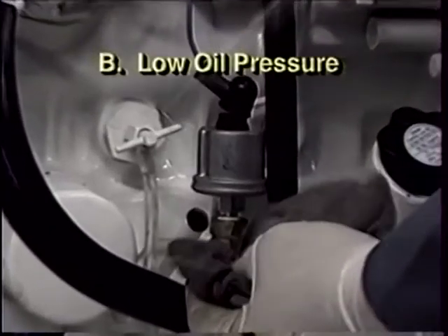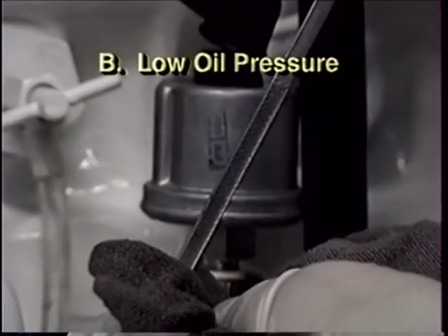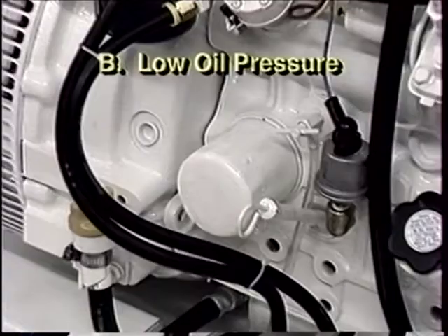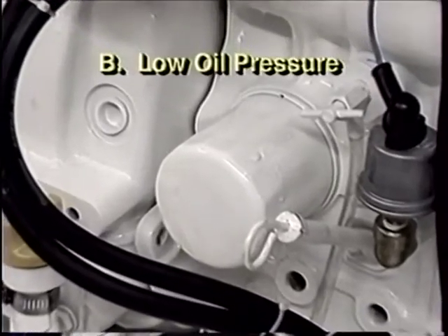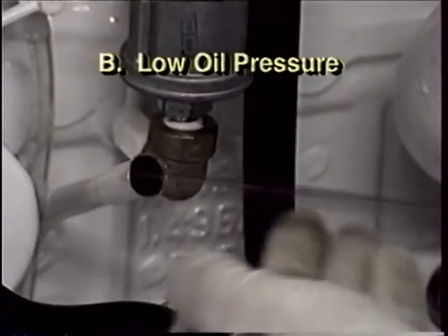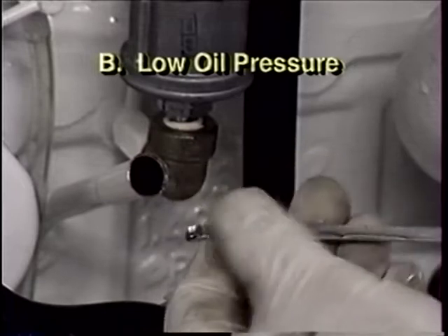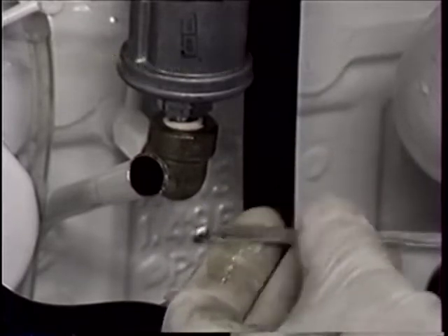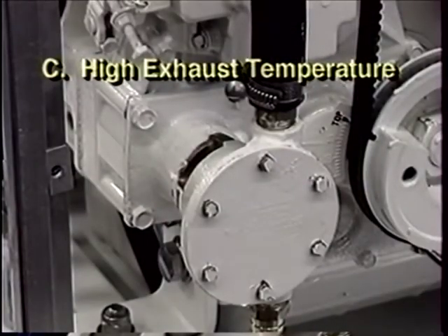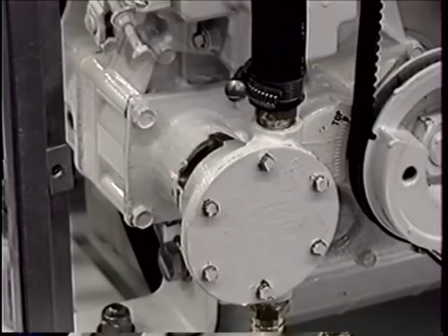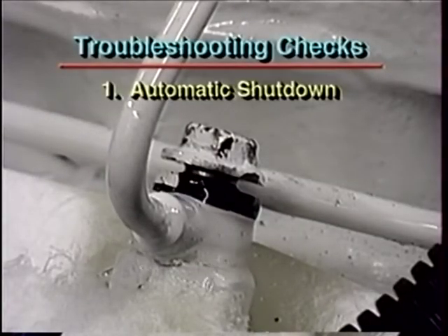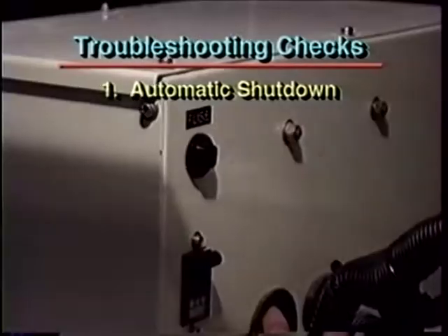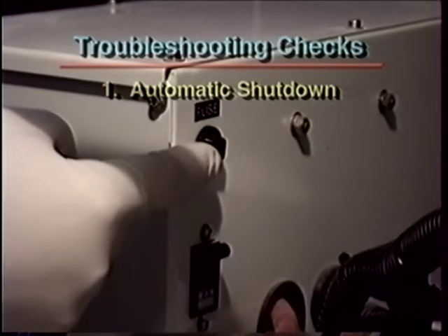Low oil pressure can be caused by a loss of lube oil, an oil filter needing to be changed, or even contaminated lube oil. If contaminated lube oil is suspected, contact your servicing dealer. High exhaust temperature is normally caused by a loss of water flow from the seawater or raw water pump. Some other causes of shutdowns can be loss of fuel or problems within the DC control circuit.